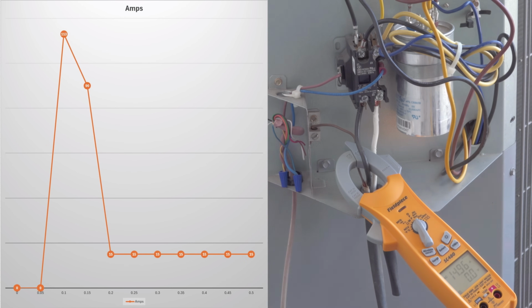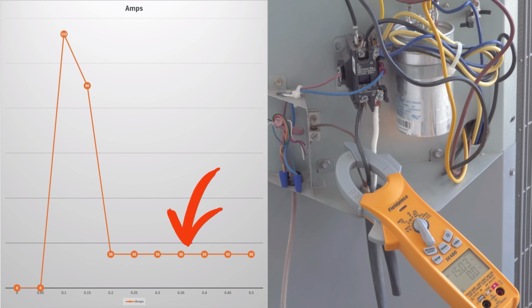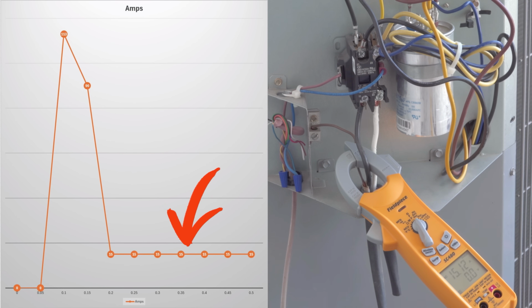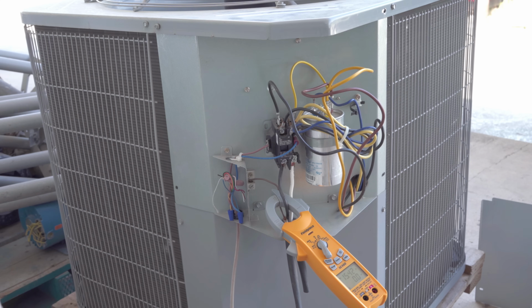Now I'm looking at the operational amps after the system's fired up, and you can see that it's running around 15 amps, so now it's kind of coasting. The bulk of the power usage is coming from the compressor, which I'm going to show you now.